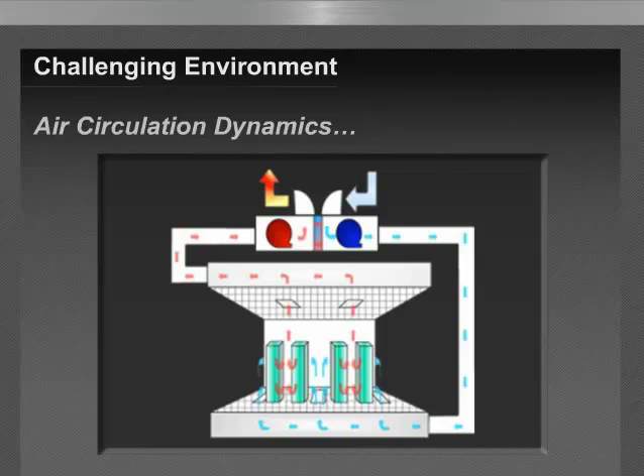And so if we look alternatively then at the other problem, and that's the use of economizers, which is great in terms of efficiencies for the facility, in terms of taking some advantage of natural cooling or free air cooling in that respect. It presents some challenges for the reliable detection of smoke. So we'll take this illustration, and if you can just imagine here that if we take a large intake of fresh air rushing into the facility, and the same effects of that air on the smoke in regards to migrating the smoke to the exit path of the air, which is generally going to be exhaust dampers leading the smoke out to the environment or to the atmosphere.